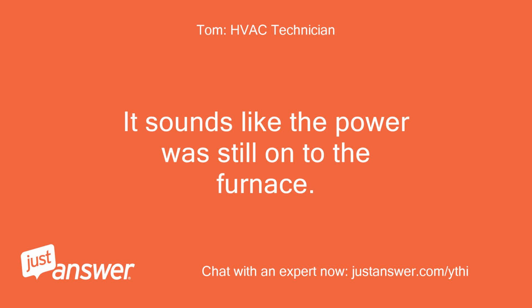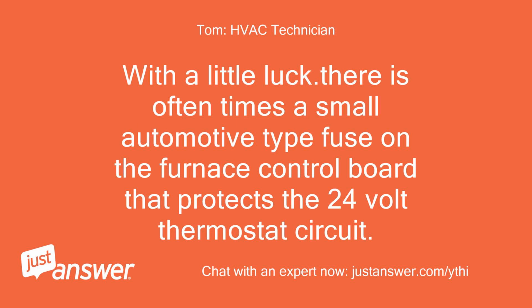It sounds like the power was still on to the furnace. With a little luck, there is oftentimes a small automotive type fuse on the furnace control board that protects the 24-volt thermostat circuit.